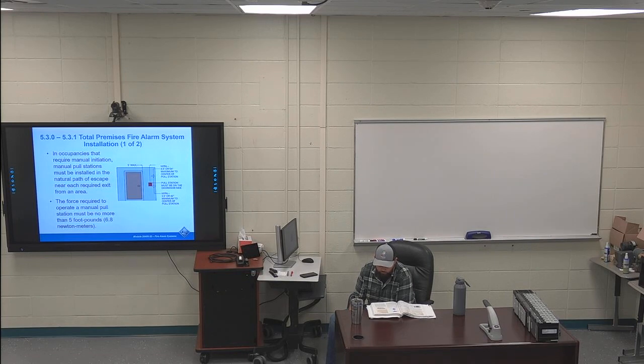An archway or doorway that extends more than 18 inches down from the ceiling greatly delays smoke travel and is considered a boundary, just like a regular wall from floor to ceiling. So that's saying if you've got a space of at least 18 inches between your door and ceiling, that's considered a boundary. So all these doors inside of this building, obviously I think those blocks are a foot, something like that. Definitely more than 18 inches between the ceiling and top of the door for these. So we can consider this a boundary.